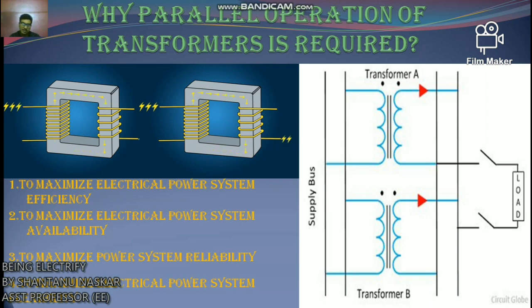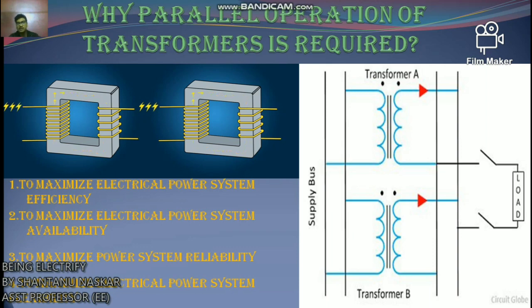Number two is to maximize electrical power system availability. If a number of transformers run in parallel, we can shut down any one of them for maintenance while the other parallel transformers serve the load without total interruption. Number three is to maximize power system reliability and flexibility. If any transformer running in parallel is tripped due to a fault, the other transformers will share the load, so power supply may not be interrupted — provided the shared load does not overload the remaining transformers.